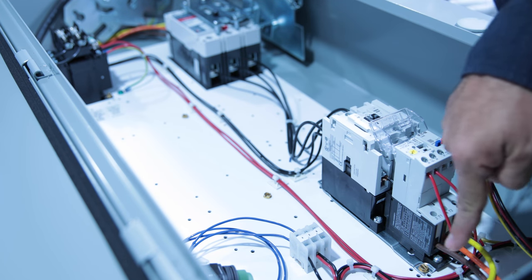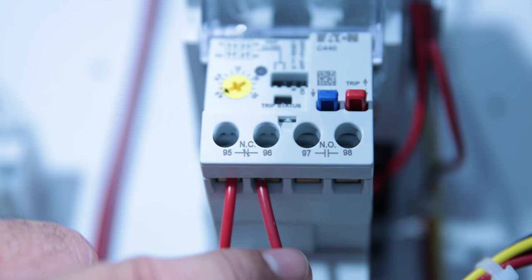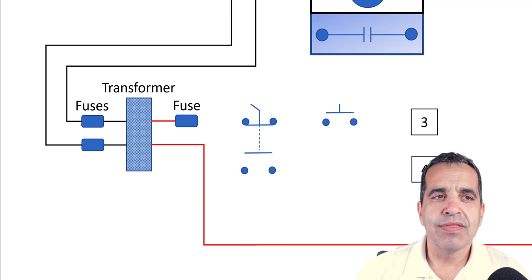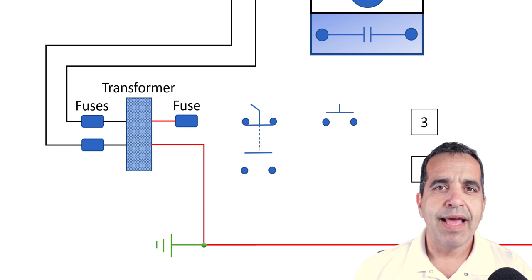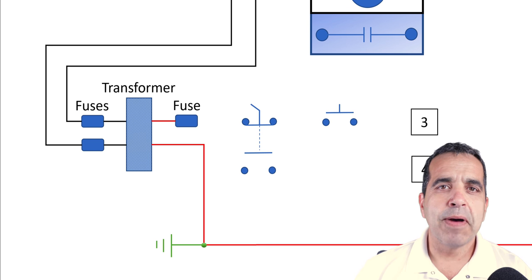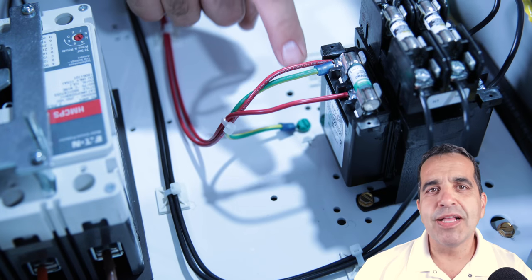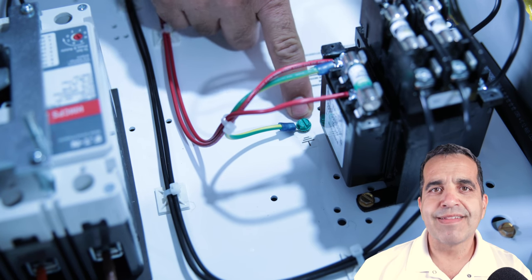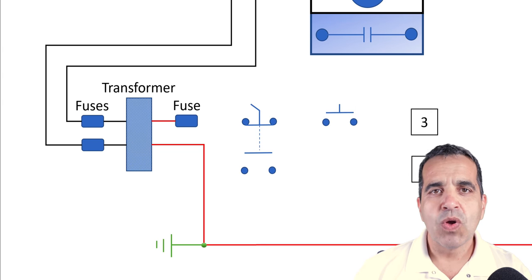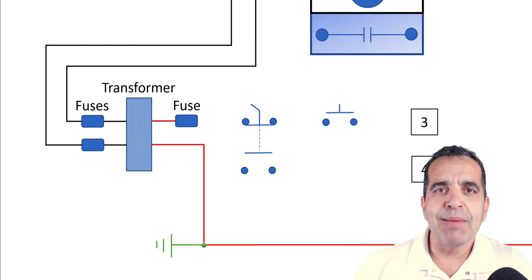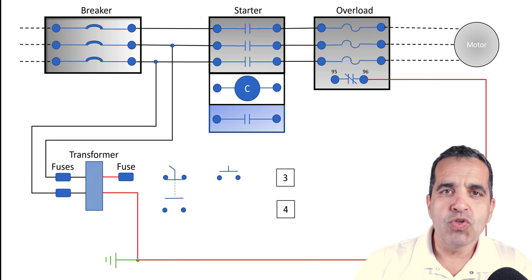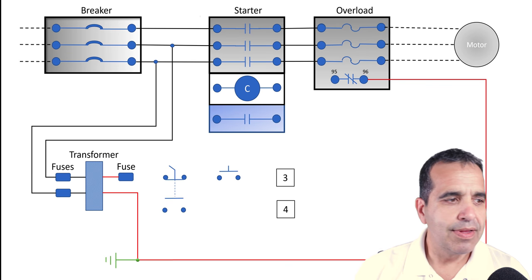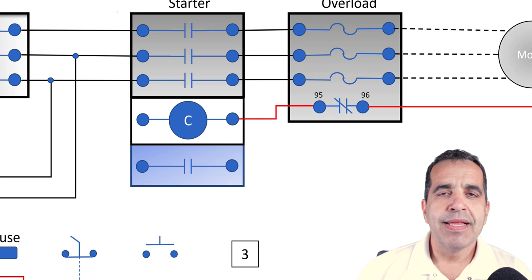The overload contact on terminal 96 is a normally closed contact. We're also showing our ground because our neutral is bonded at the transformer to the case of the pump panel. It needs to be bonded with the ground because a transformer is a separately derived system—we're deriving a new voltage, so we must bond the neutral once again after that neutral has been created.